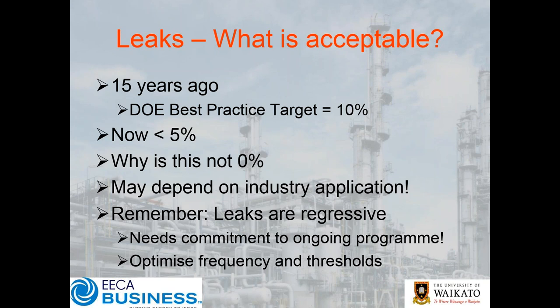Ultrasonic leak detection technology is well established and well used. It takes you beyond just fixing the leaks you can audibly hear — it's now about fixing the leaks you should be fixing because you can determine where they are. The reason this target isn't actually zero percent is that if you've got zero leaks, you have to ask yourself: are you overspending on your maintenance budget versus what those leaks are actually costing you? There is an optimization in terms of your spend. Leaks are a regressive opportunity, meaning it's something you have to commit to on an ongoing basis — you need to set up a program to keep them in check.